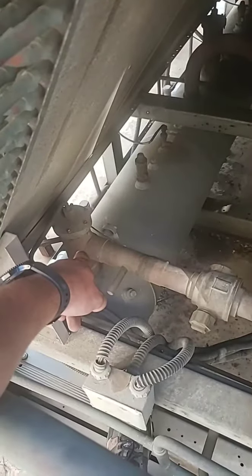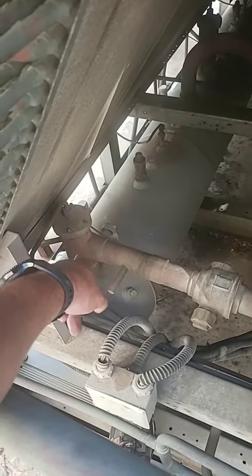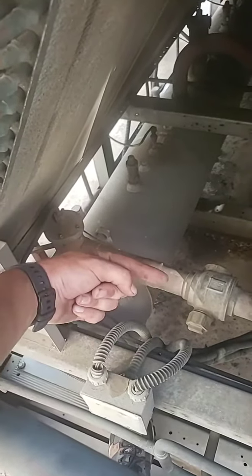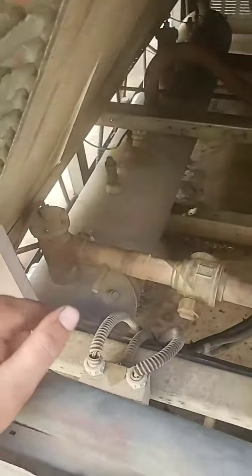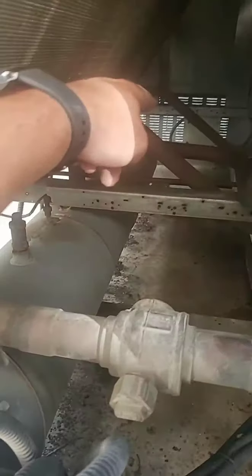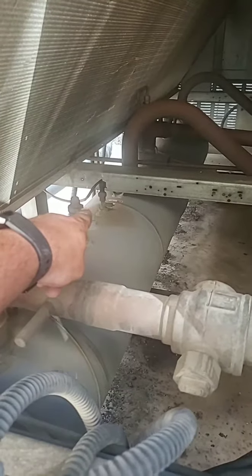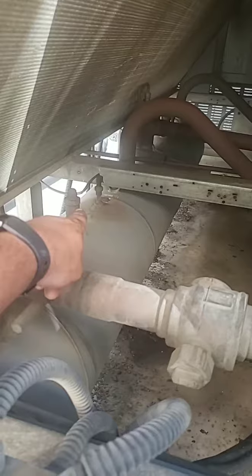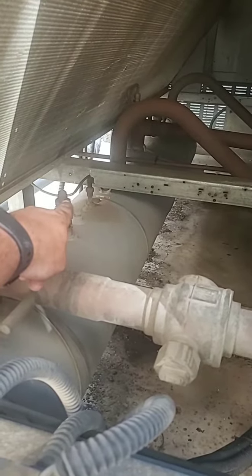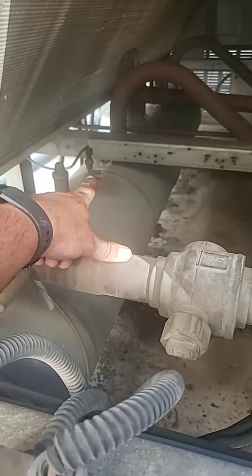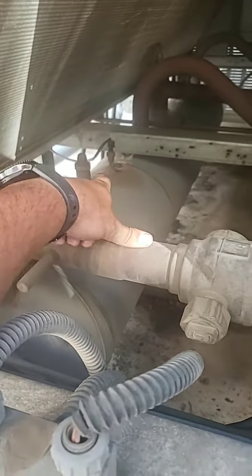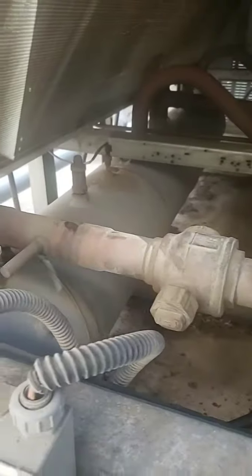This right here is your oil separator check valve. The flow is coming out this way, so if it ever senses any kind of backflow, it will check right there and prevent that. This is circuit B, the side closest to us. Down there on the far end, that's your circuit A. That transducer right there is your oil pressure transducer. I'm sorry, that is your high pressure transducer, on your condenser side, not oil pressure. That's your high pressure transducer. So that's your oil separator.